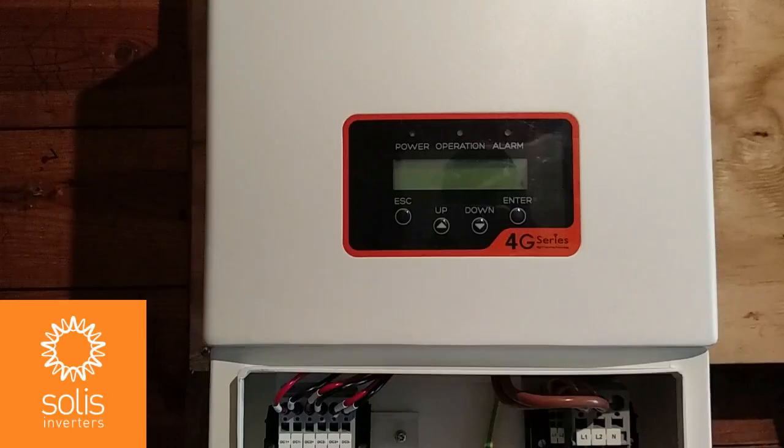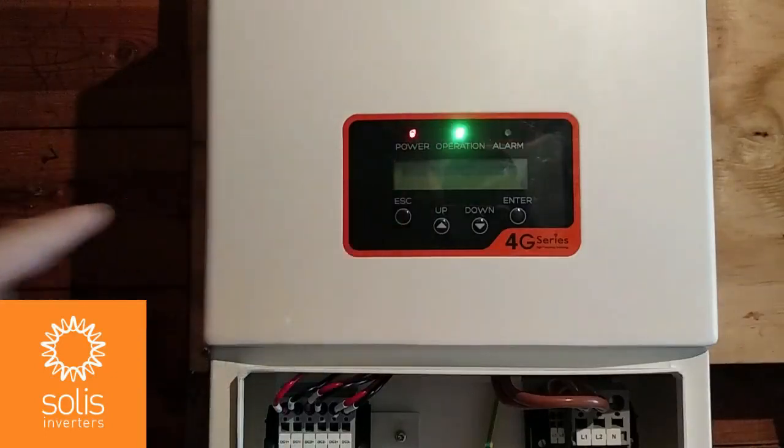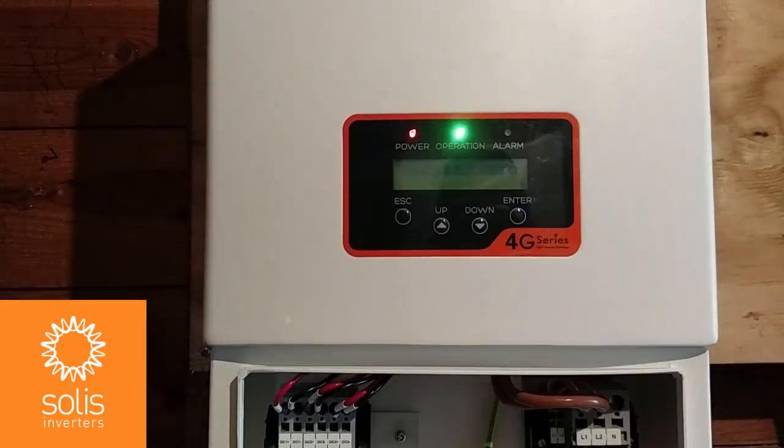Now I can turn on the integrated DC disconnect switch on the bottom of the inverter to the on position. Solis inverters are DC-powered devices, so as soon as you apply PV power, the red power LED will come on. You can also see the green operation light comes on and begins to blink — over the next five minutes the inverter will prepare for energy generation. After the inverter starts up normally, you can go into the information menu to review system operations or the settings menu to change the time and date. Reinstall the wire box cover to complete the installation of the Solis single-phase inverter.